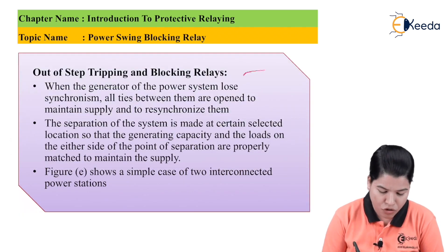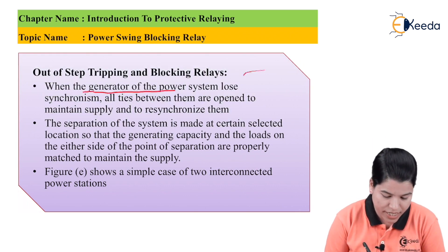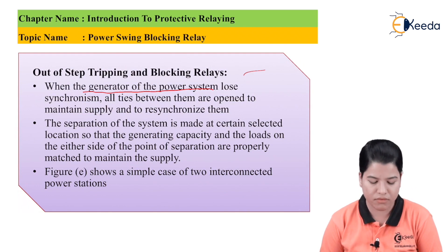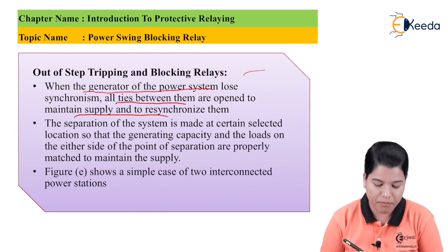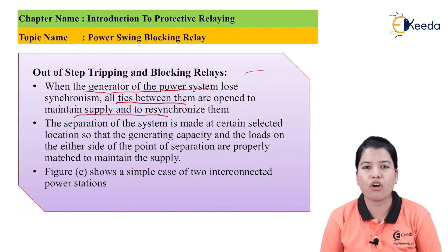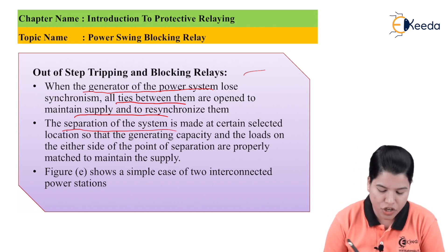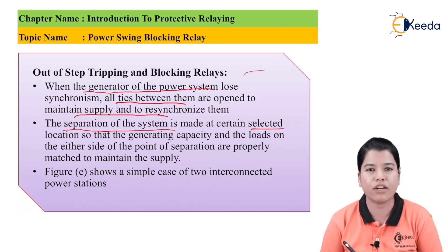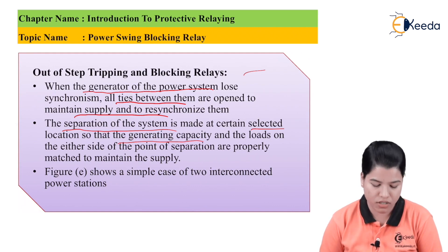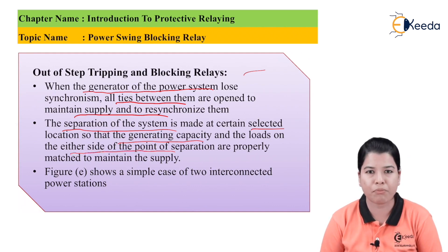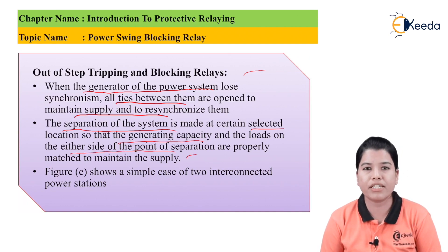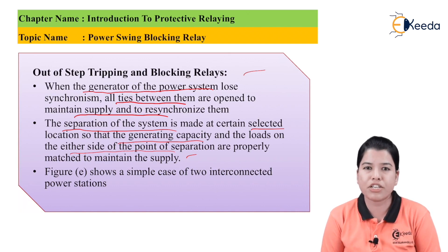Now let us study out-of-step tripping and blocking relays. When the generators of the power system lose synchronism, all the ties between them are opened to maintain supply and to resynchronize them. The separation of the system can be made at a certain selected location so that generator capacity and loads on either side of the point of separation are properly matched to maintain the supply without interrupting consumers.